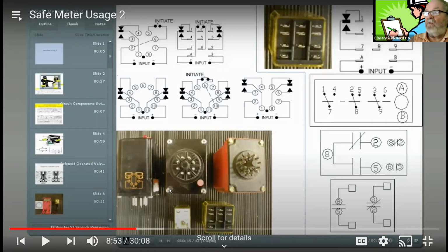If you remember doing a single pole double throw, we had 5 terminals. We had 2 of them from our coil, then we had C for the C contact, and then the NO and NC. That was 5 terminals, a single pole double throw. If you go to a double pole double throw, we're going to have 3 more terminals for that set of contacts we're adding. So you're adding 3 to that 5, and that gives us 8. And then you're going, okay, maybe I want a triple pole of my double pole. So you add 3 more contacts, and that gets you 11. So you've got your 11 pin relays, your 8, and so on and so forth.